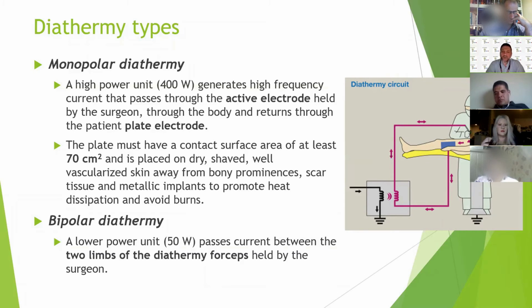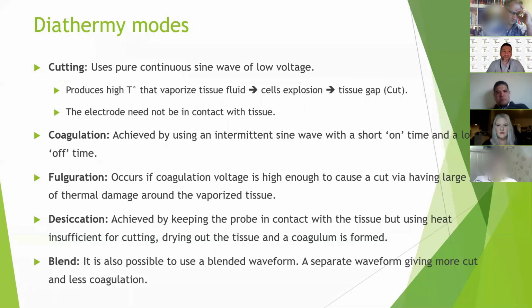It has to be put away from any bony prominences, scar tissues, metallic implants, and definitely away from the heart. And make sure that the current does not pass anywhere near the heart, especially if there are implantable devices. The bipolar diathermy, however, does not need that plate, and the current passes through the two arms of the forceps. So it is only in that area, and it has lower energy. So it's 50 watts compared to 400 watts for the monopolar.